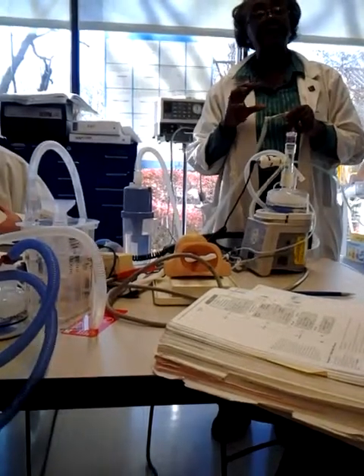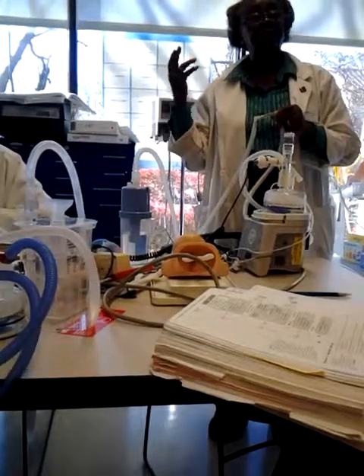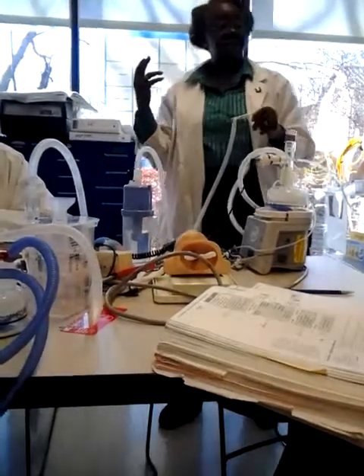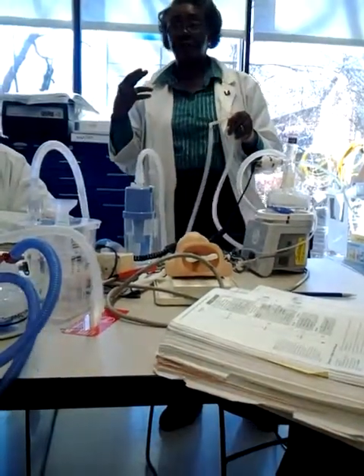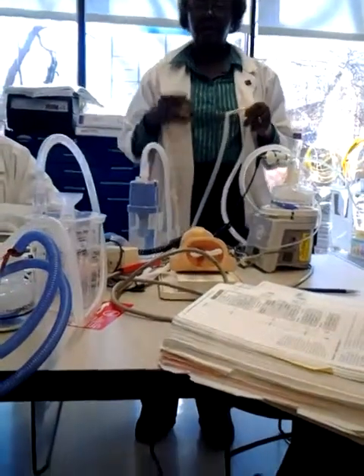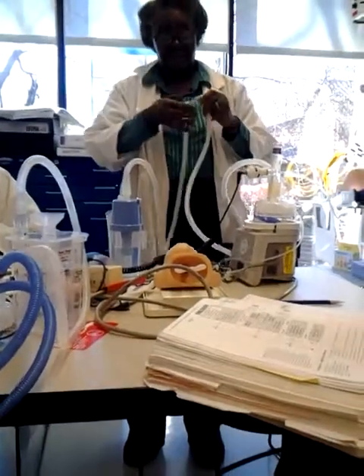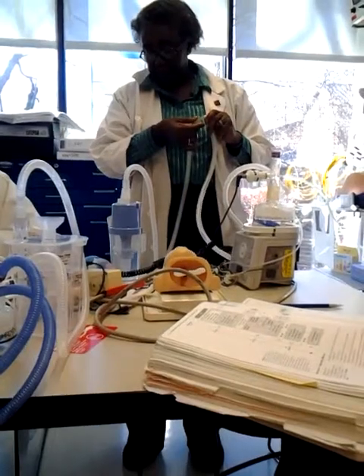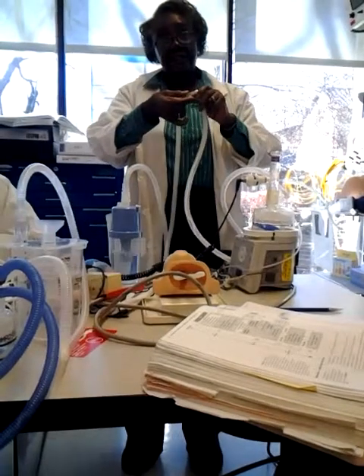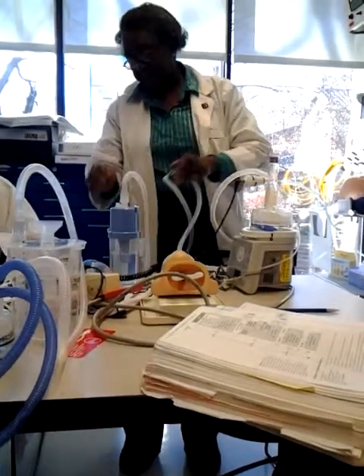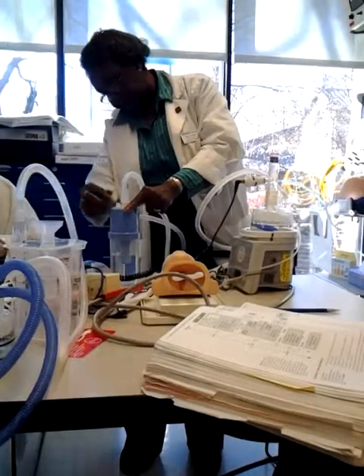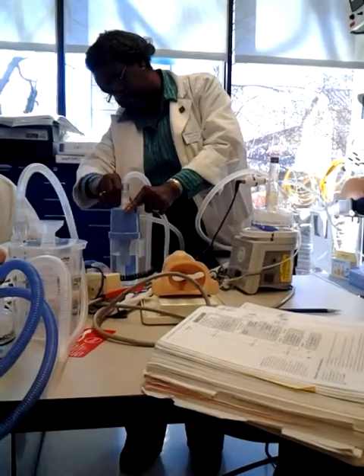The only way you can tell there's a problem is if the baby's alarm monitor goes off and their saturation starts to drop or they become bradycardic or tachycardic because of lack of oxygen. But by applying pressure, if I have a closed system, then I'm getting the bubbles. Now I'm going to go up to 5 centimeters of water. Let's go to 6, and you'll see this is going to go further down into the water.